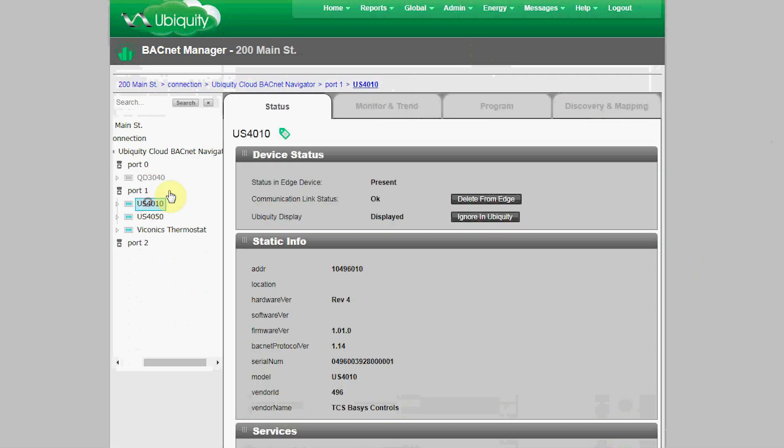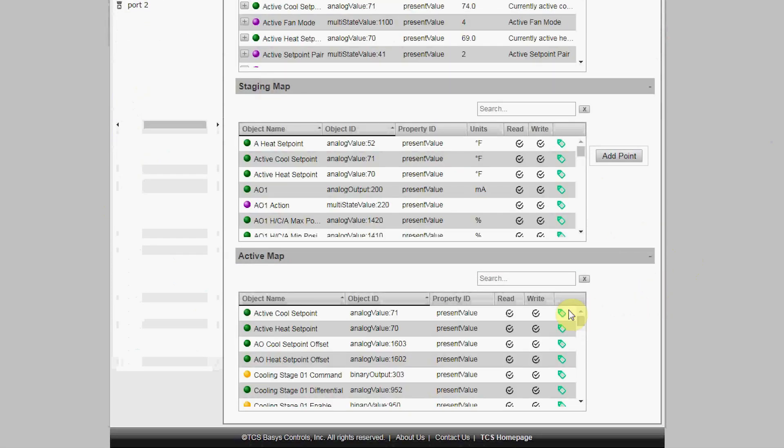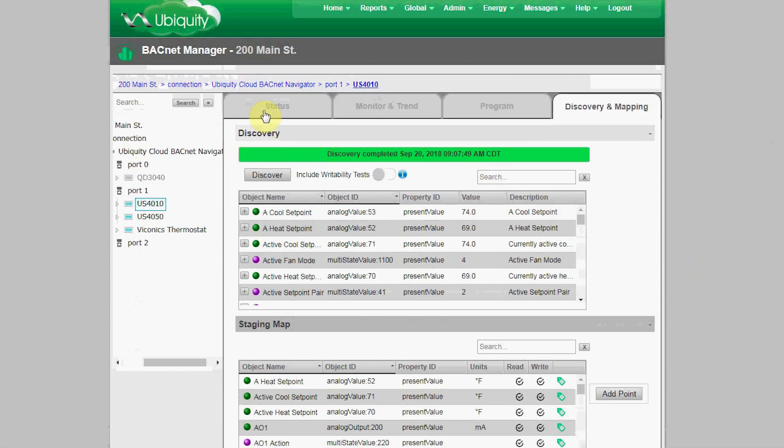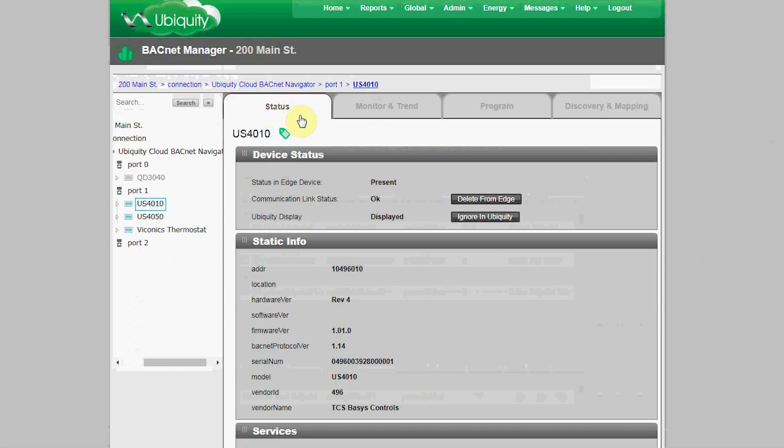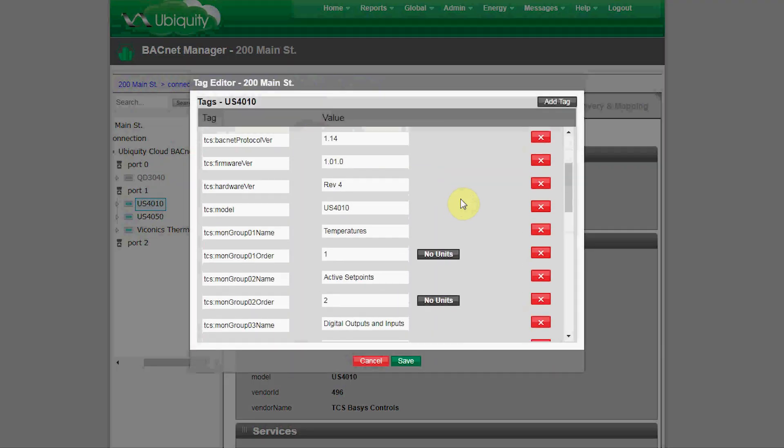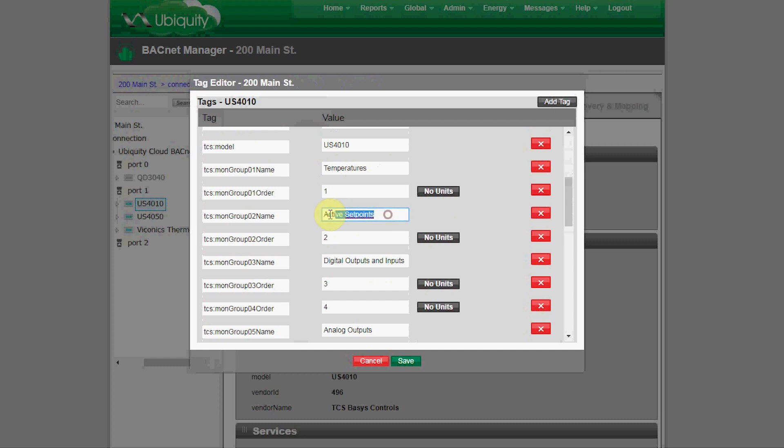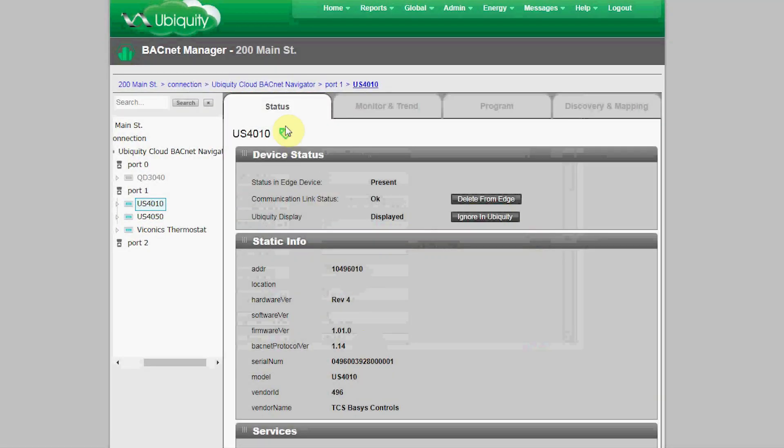As an admin, you can change those pages as needed by adding or deleting tags. That's how I used this to set up the 4010 after it was auto-detected and all those tags came in. I set up the defaults and I set up the group names I wanted to use in the device tagging interface. You can see how I set up temperatures in the monitoring group in the first position, active set points in the second position, and so on. That's using the tagging for the device itself, the US 4010 device.